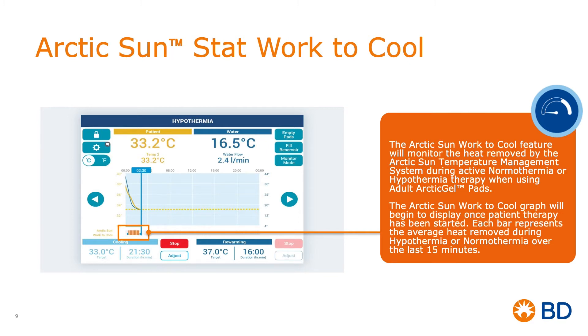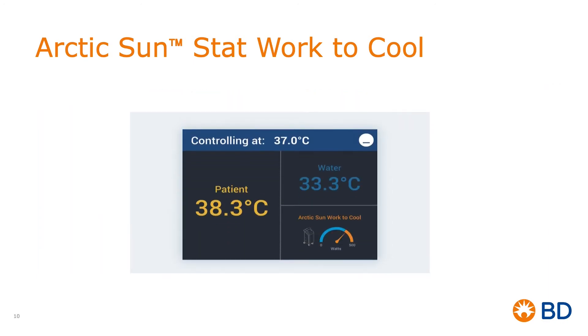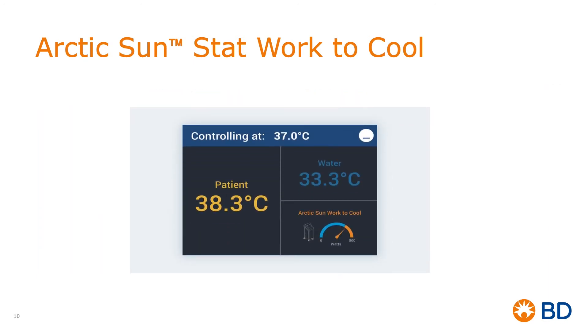When the gauge is displaying orange, it is an indication that the system is working hard to cool and that the patient should be assessed for shivering, seizure, fever, internal bleeding, or other causes of heat generation. The Work to Cool gauge is also displayed on the lock screen, providing real-time feedback about your patient's response to therapy.